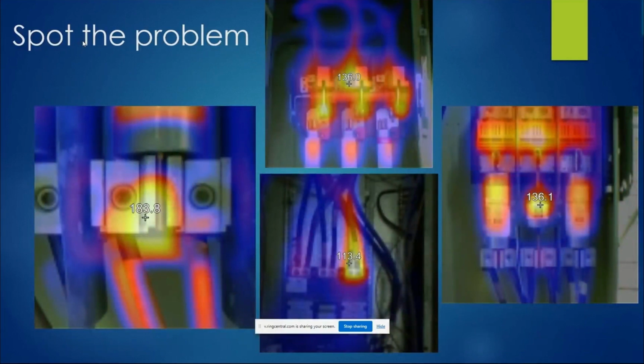If you're looking at these 4 slides for the problems, I think most of you who may be exposed to this kind of thing on a regular basis can identify what's going on. But these are things we're looking for, and things I would put in my report for you. The one on the far left is a termination issue. Right there, that hot spot is a definite sign of a poor termination. It could be a loose lug. It could be a wire where they secured the lug on top of the insulation and didn't make a good connection onto the lug. There are multiple reasons for that high heat signature, but 183 degrees is definitely a key point where I would say this is a severe problem. At the next available weekend or whatever, you need to shut this piece of equipment off and redo that connection. The 2 middle frames are showing you some more heat signatures from overload conditions. The one at the bottom is an imbalance.